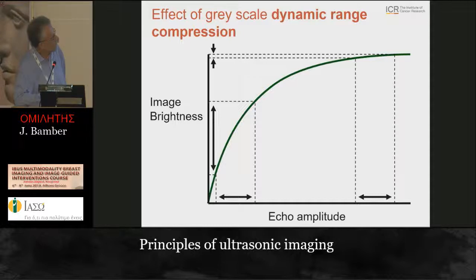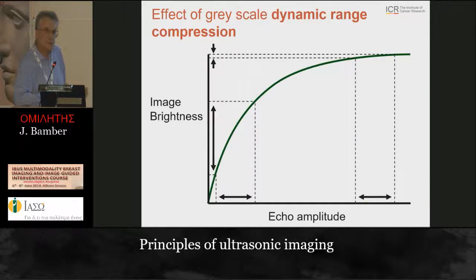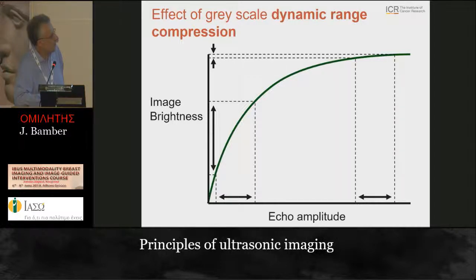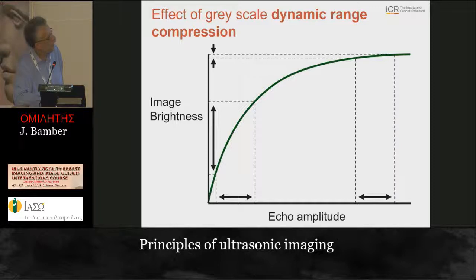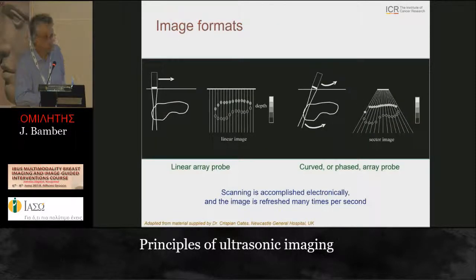This relationship is adjustable - it's called the dynamic range control, which we'll play with in the hands-on demo. An important point: at low echo amplitudes, a wide range of amplitudes translates to a big range of image brightness, making it easy to distinguish between them. But at high amplitudes, the same range translates to a very small range of brightnesses, making discrimination very difficult - worth bearing in mind when interpreting images.